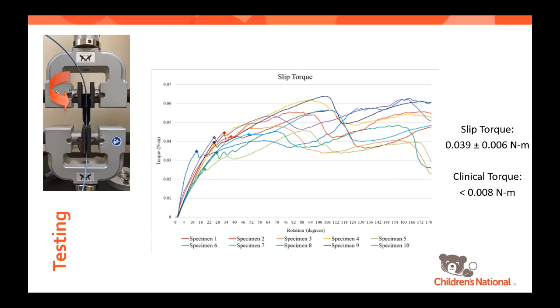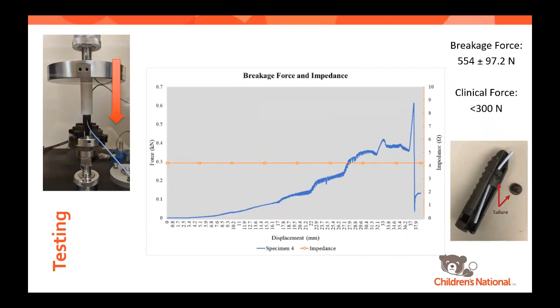Next, we investigated catheter performance at maximum grip strength. The sled was advanced to the point of failure while simultaneously recording catheter impedance and a simulated ablation waveform delivered through the catheter. The tool experienced failure at an average force of 554 Newtons, nearly 2 times the force that can be generated by a human. There was no statistically significant change observed in catheter impedance or the simulated waveform.